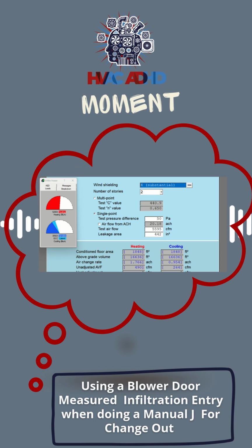So you either A, have to seal the house up, or B, you have to think of a different strategy to handle some of that water and handle this heating load. So two totally different stories depending on if you use loose, which is the loosest thing you can use if you're not using a blower door, or if you actually measure the blower door.